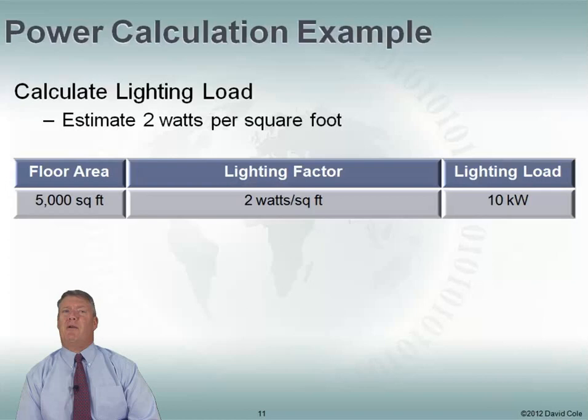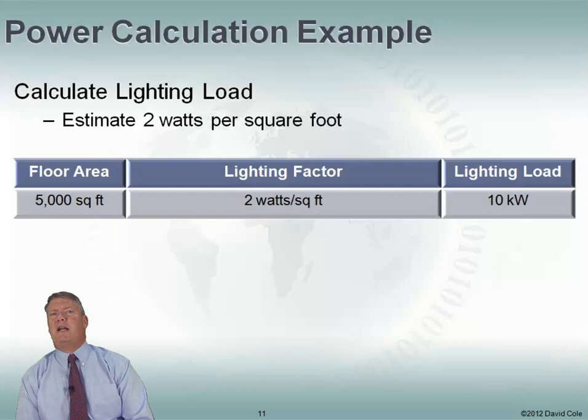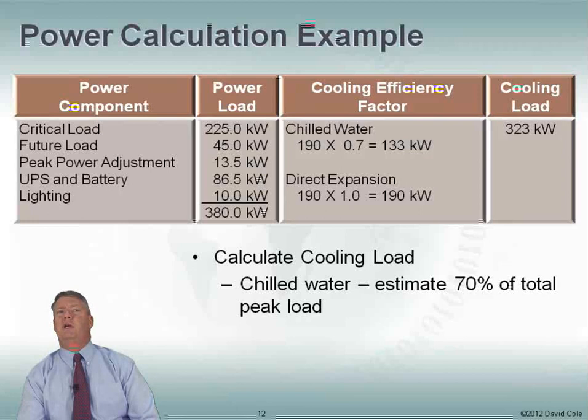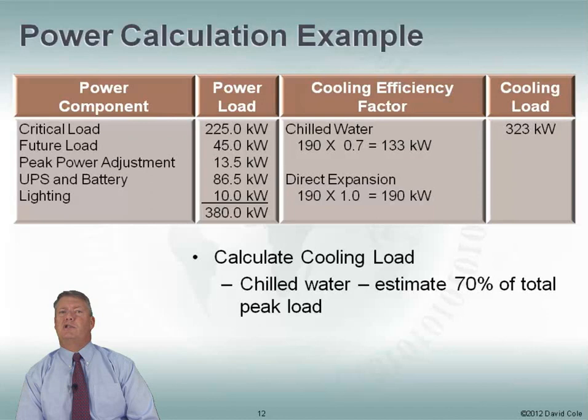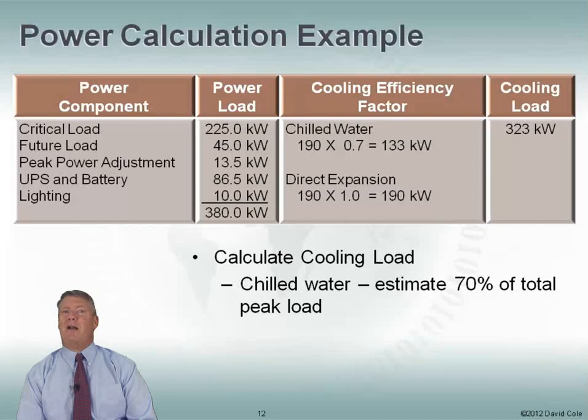Now let's look at lighting. For lighting purposes, we estimate about 2 watts per square foot. We have 5,000 square feet at 2 watts per square foot — that's 10 kilowatts for our lighting load. Now we start adding all of these up: our critical load of 225 kilowatts, 20% for future load, a peak power adjustment, UPS and battery overhead, and lighting. And now we're up to 380 kilowatts.